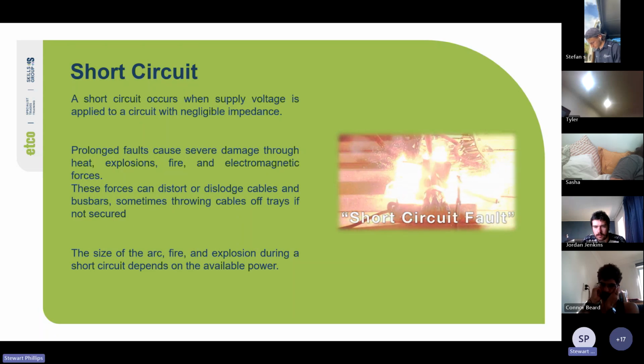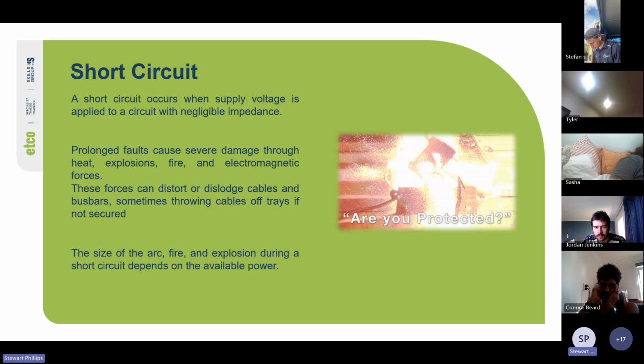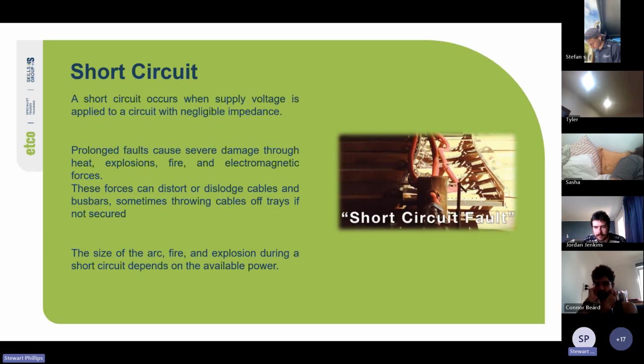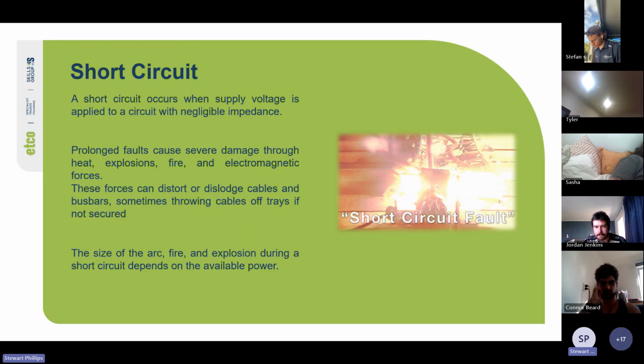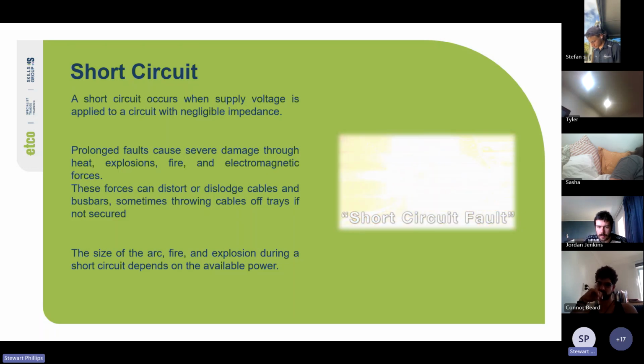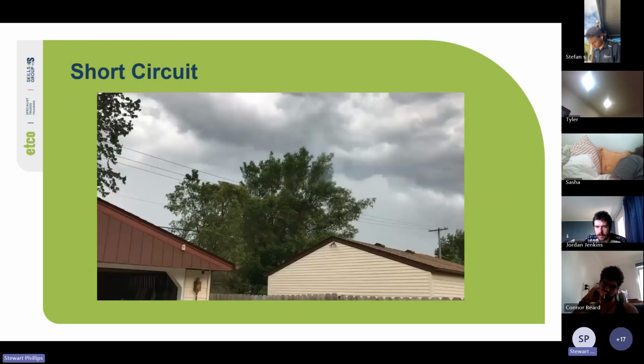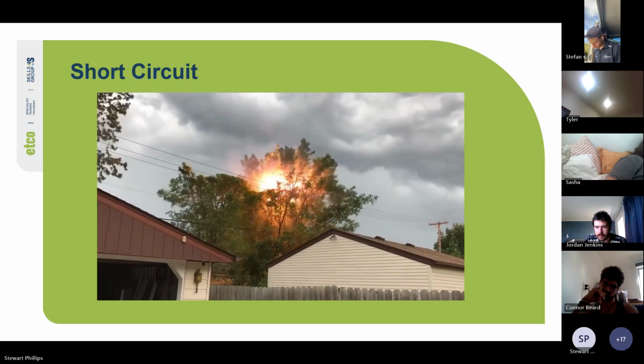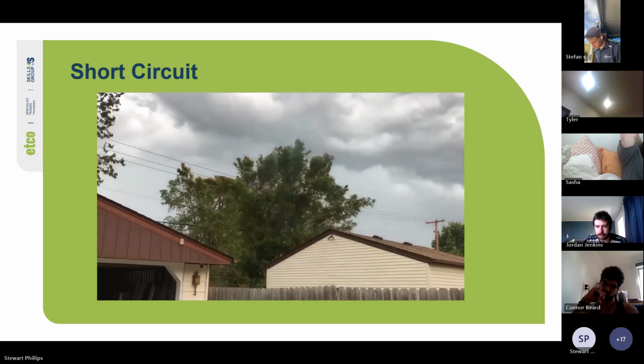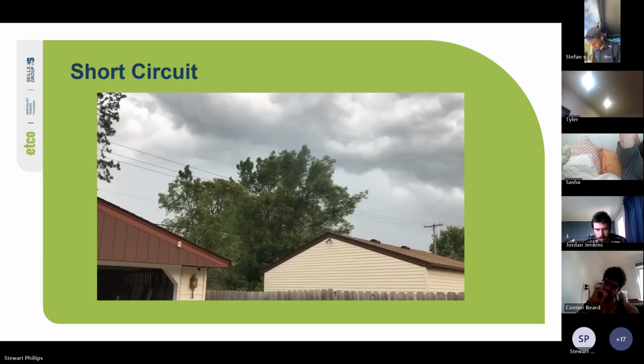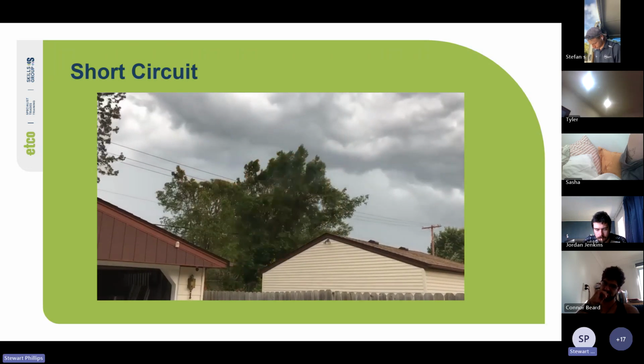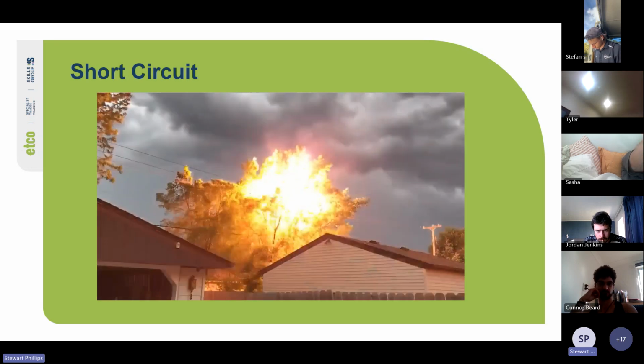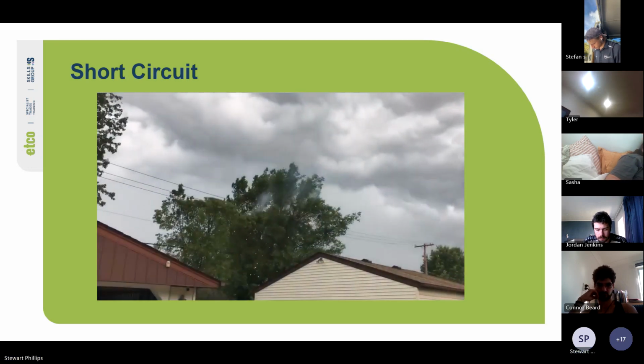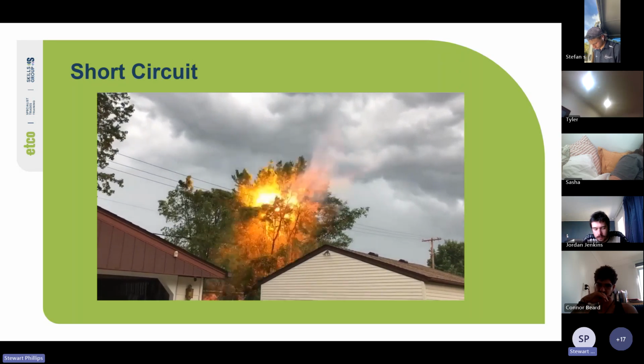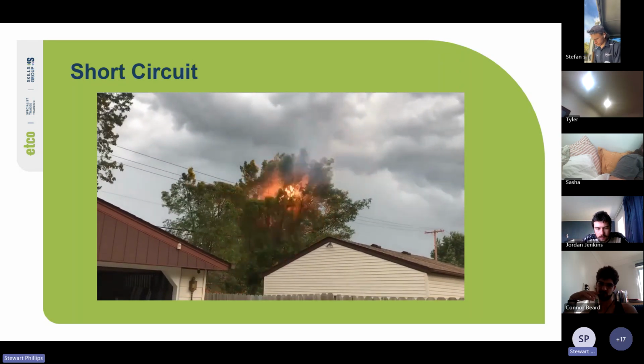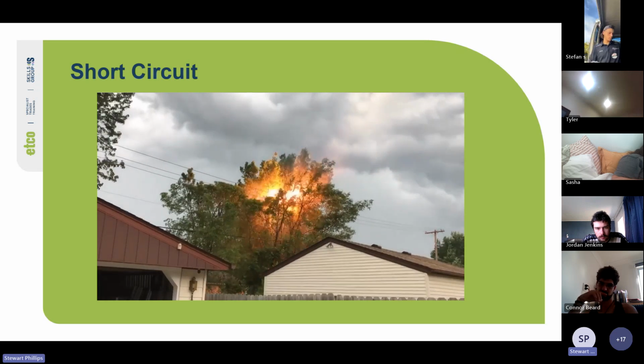And those of you can see that. So yeah, that's big meaty cables on a cable tray and a short circuit. And as you can see, there's a lot of force that can be applied because that cable ladder is bending like nothing else. Cool. And then yeah, so trees near overhead power lines can cause arcing. It can get so bad that arcs form, trees catch on fire, and then eventually the high voltage line or overhead line will snap.